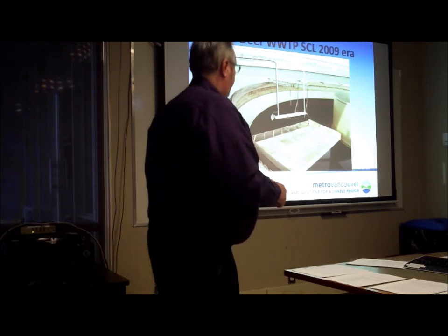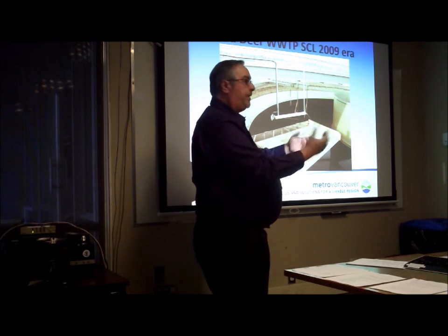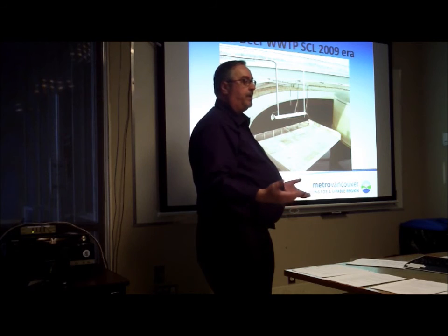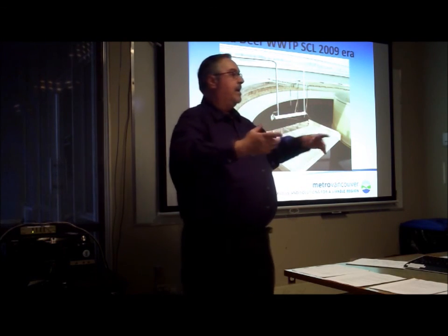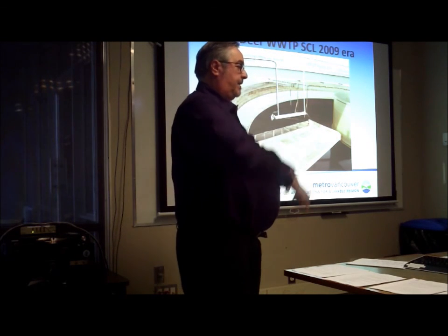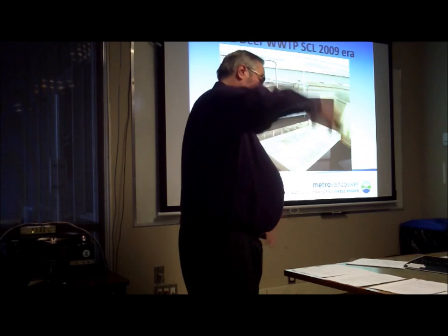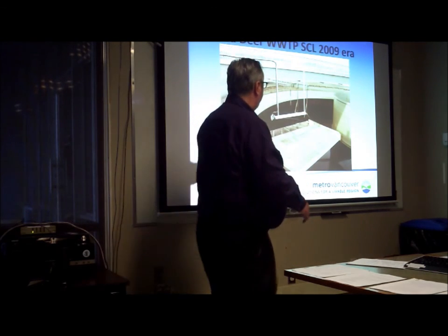You know, the way that the mixed liquor comes up the center column, goes out that energy tub into the flocculation well, and it forces the currents down. And the idea is that the currents will go down, possibly, maybe not to the floor of the clarifier, but then they'll deflect off the floor and come up the side and then over the overflow weir.